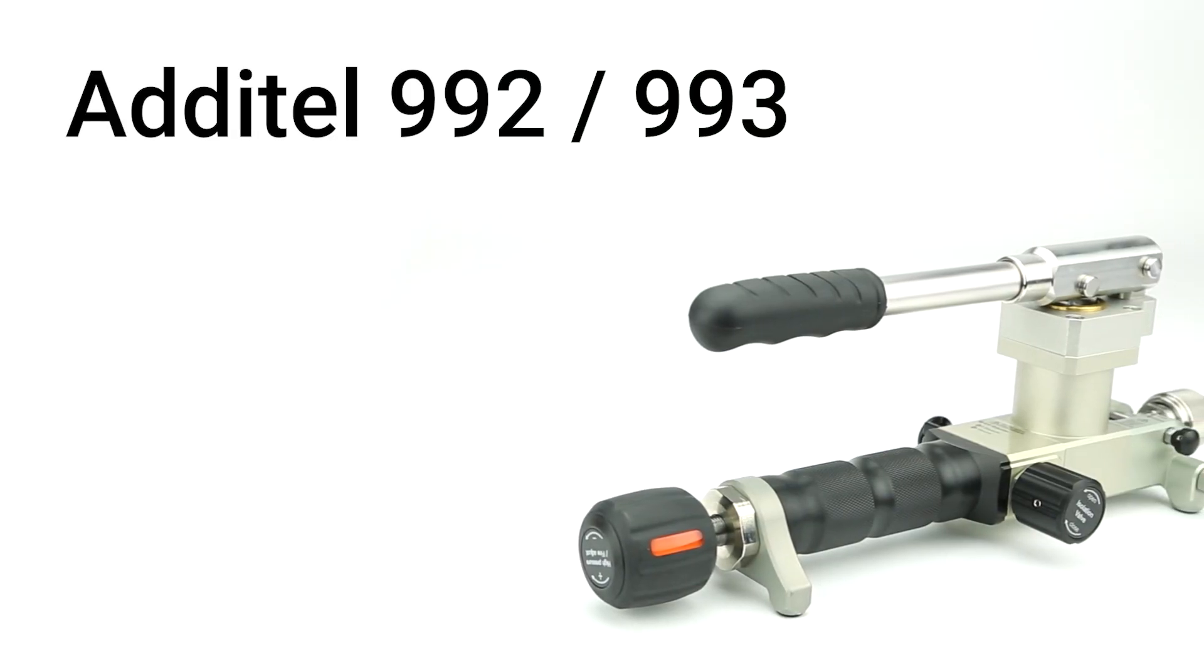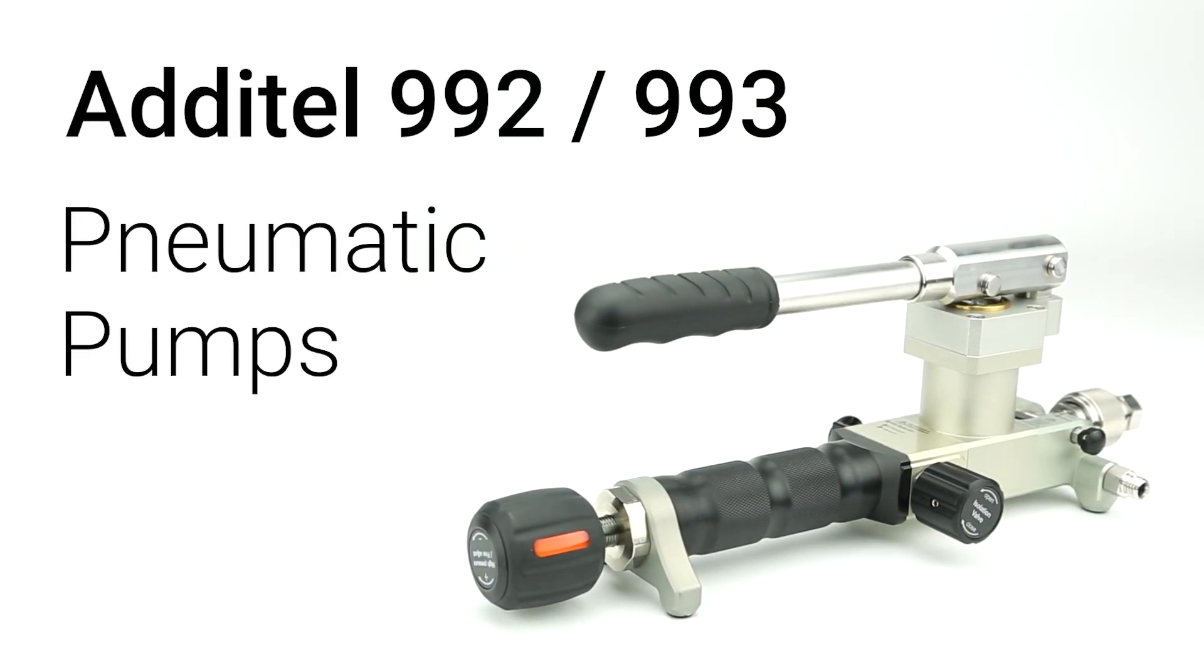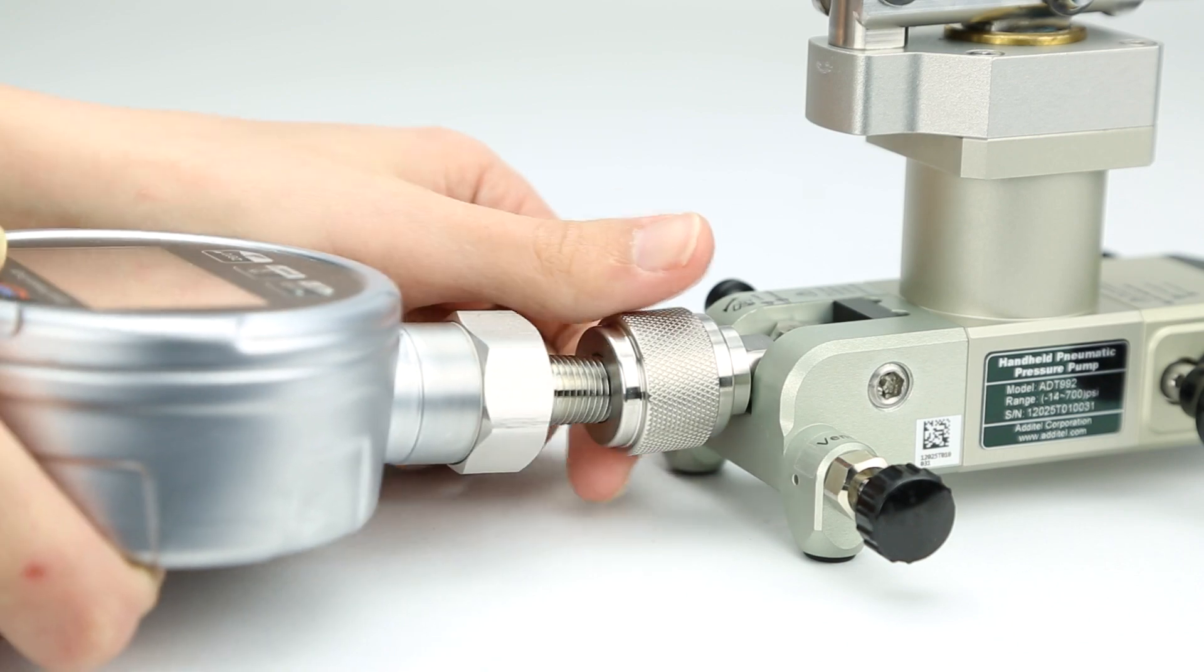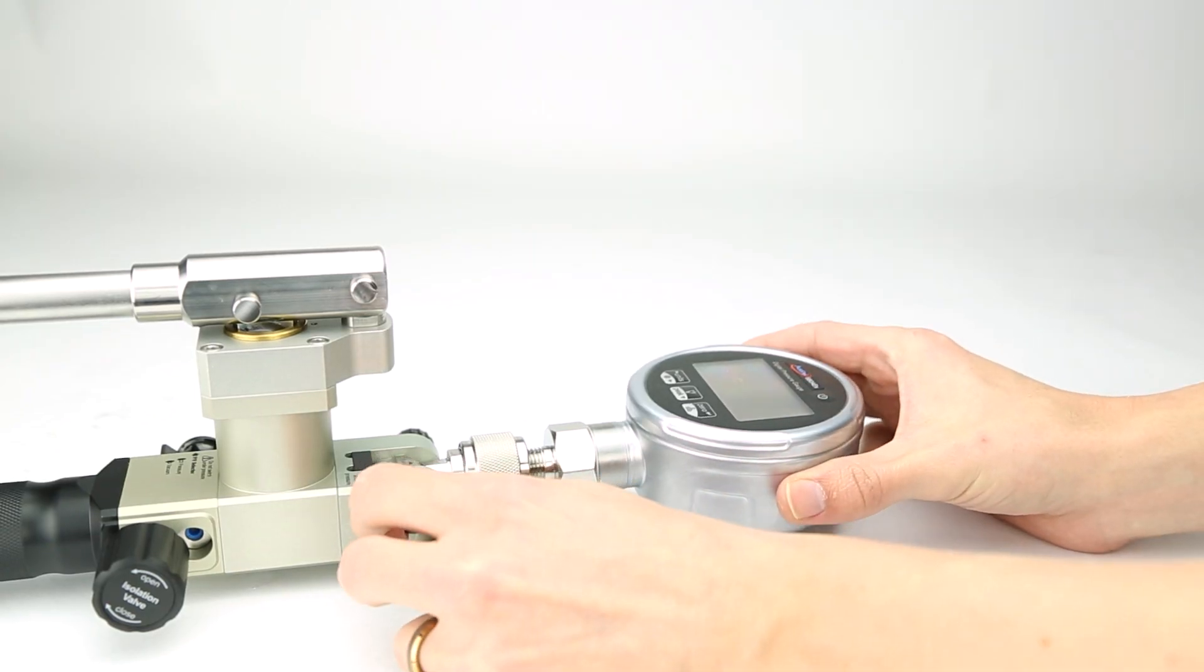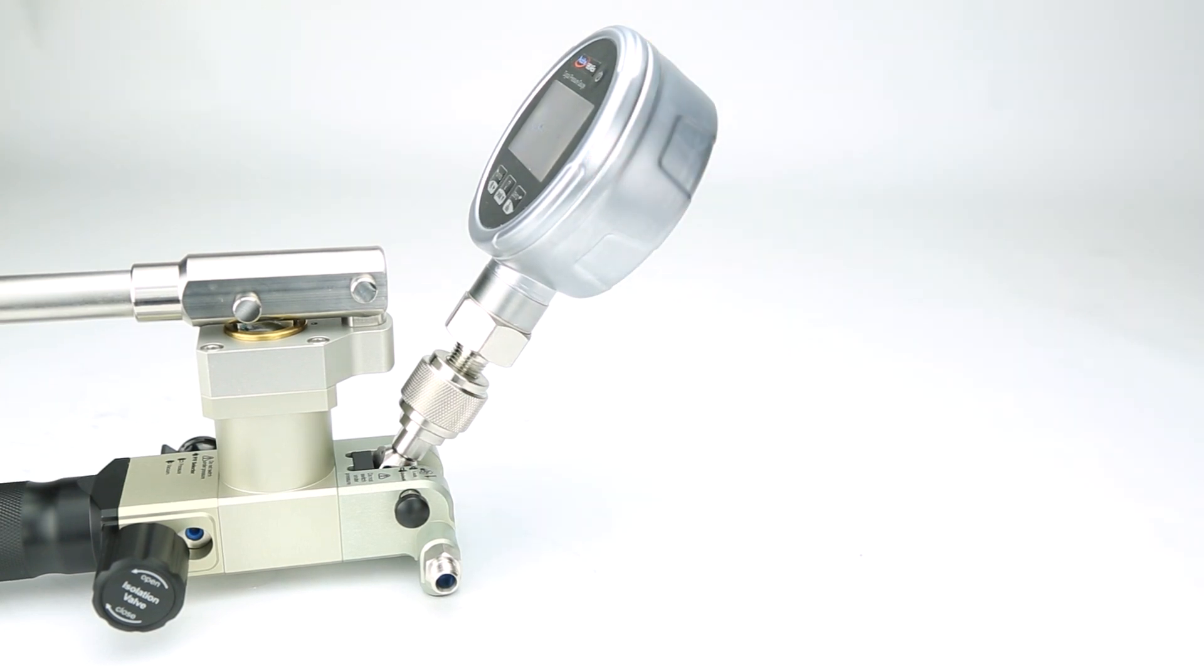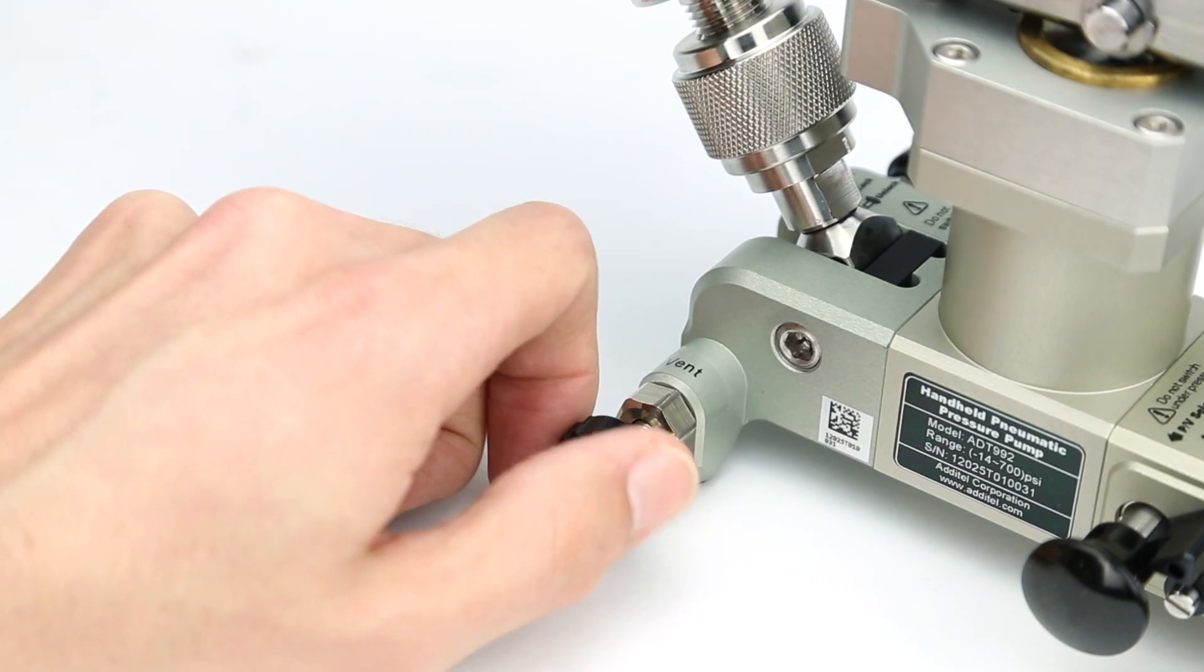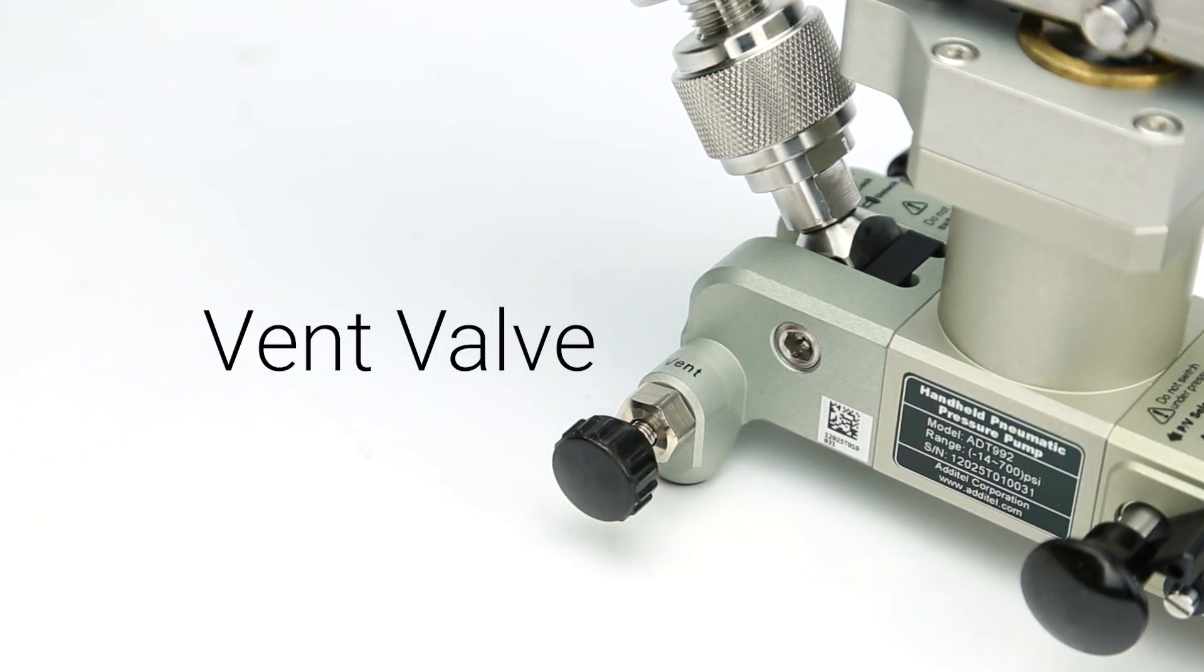Let's take a closer look at the operation of these pumps, starting with the pneumatic models. To begin, attach a reference gauge to the adjustable port and change the position according to the desired orientation. To maximize the longevity of the seals, it's advised to only change the reference port position while the pump is not under pressure.